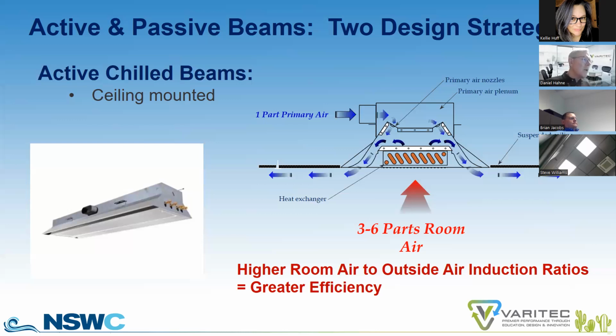To design a beam and to maximize its efficiency, you want to increase the induction ratio of room to outside air as much as possible. And that is a question of how do you select your chill beam? You really need to know how to select a chill beam. I've seen many jobs where beams are selected where the beam is designed at max GPM flow. That beam has nowhere to go if there are space contingencies that demand greater capacity. So consequently, it could compromise the performance and result in complaints of thermal comfort conditions. Design your GPM flow rate at a medium flow rate so you can either increase or decrease the chill water flow rate to increase or decrease cooling or heating capacities.